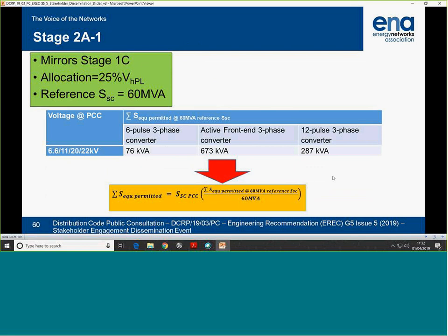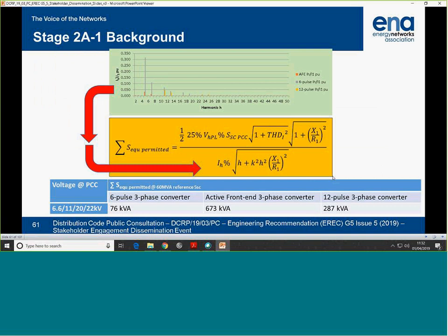Formula is basically the same as we had for 1C, but instead the figure on the bottom now is 60 MVA because it's on that basis. So you can happily skip over that. The formula to derive the value is different. Actually, that 1/2 factor is reflecting that you've got less equipment connecting at higher voltage. That's why that's there.